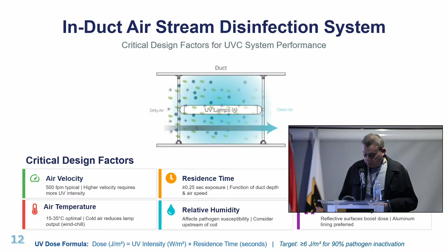One thing that was also found out is that the lower the temperature of the air, the less effective the UV light is. It gets degraded with lower temperature. So considering all these factors, we went back to the same air handling unit. We decided to place these lamps in the mixing air plenum, where you have the return air coming and mixed with the fresh air. Why? Because we have the lowest velocity. We have 500 feet per minute across that plenum, and it's a huge plenum, and this is where we decided to put these lights. Also, the air temperature is not as low as downstream from the coil.